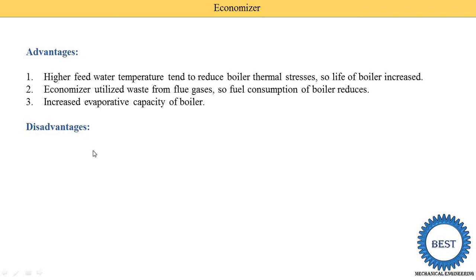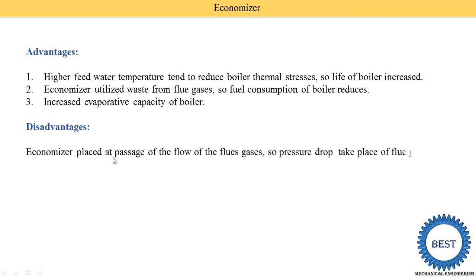The disadvantages of the economizer are: the economizer is placed at the passage of the flow of flue gases, so a pressure drop takes place in the flue gas and there is a loss of draught. To compensate for this, we are required to put a fan in the flow of the exhaust gases. This is the disadvantage of the economizer.